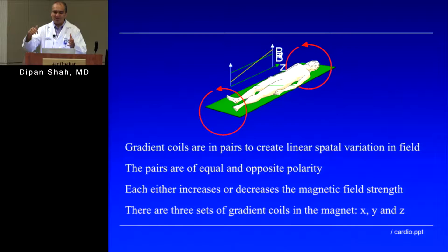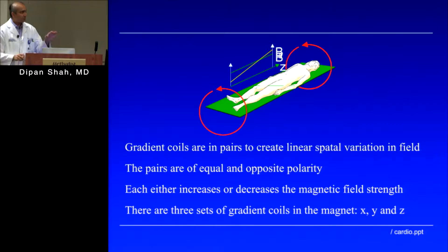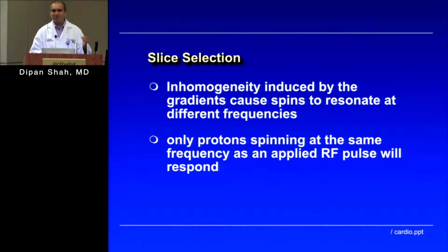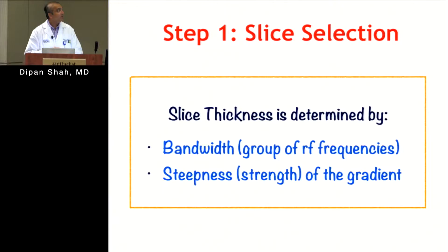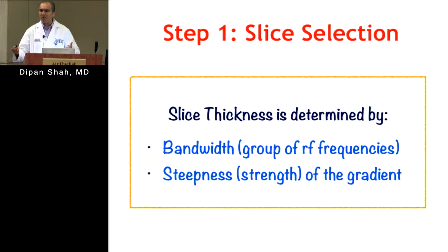The slice-select gradient allows me to pick the slice I want to image by applying this gradient and sending in an RF pulse at the frequency corresponding to that specific location. The thickness of that slice is determined by the bandwidth and the steepness of the gradient. The basic concept is simply slice selection, made possible by applying a gradient — without the gradient, all protons spin at 64 megahertz and there's no selective excitation.